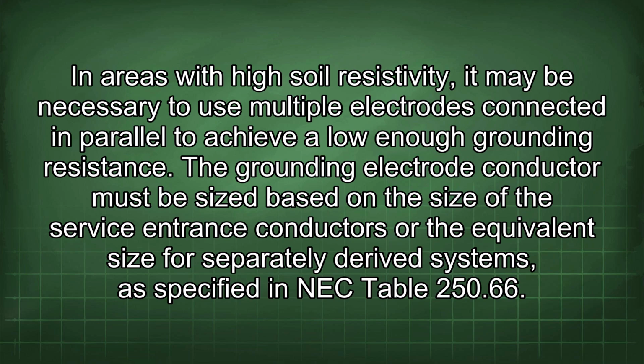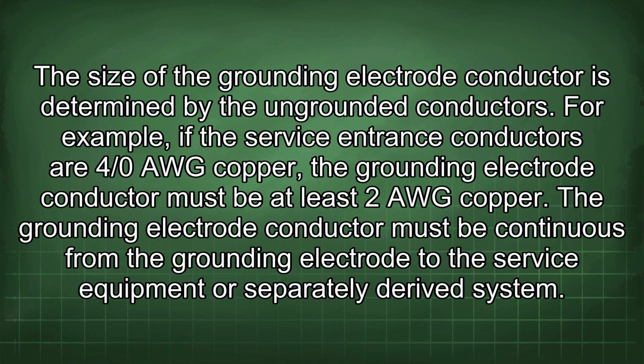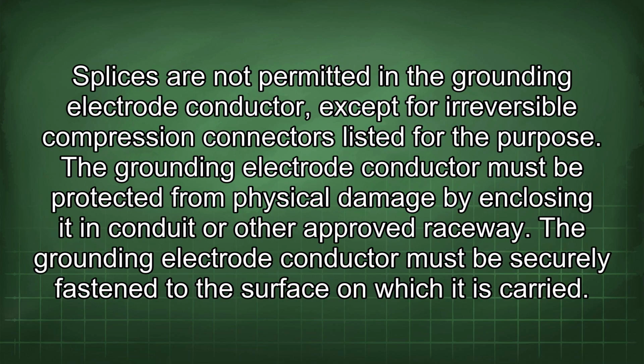The grounding electrode conductor must be sized based on the size of the service entrance conductors or the equivalent size for separately derived systems, as specified in NEC Table 250.66. The size of the grounding electrode conductor is determined by the ungrounded conductors. For example, if the service entrance conductors are 4/0 AWG copper, the grounding electrode conductor must be at least 2 AWG copper. The grounding electrode conductor must be continuous from the grounding electrode to the service equipment or separately derived system. Splices are not permitted in the grounding electrode conductor except for irreversible compression connectors listed for the purpose.